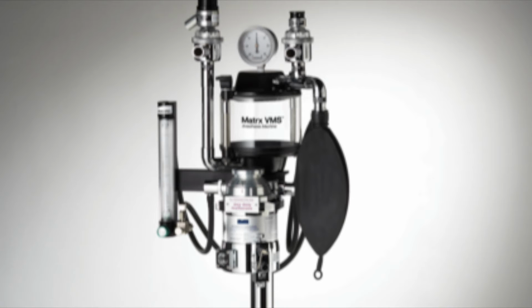The F-air canister contains activated charcoal and absorbs waste halogenated anesthetic gases, and O2 and carbon dioxide are vented out of the bottom. It must be elevated off of the surface or floor as gas is vented out of the bottom of the canister.